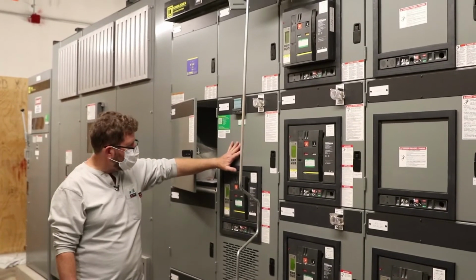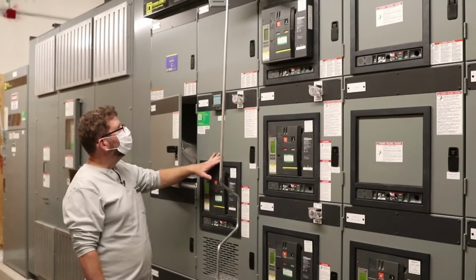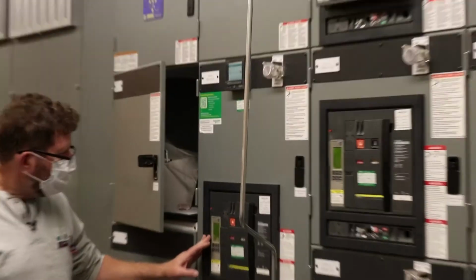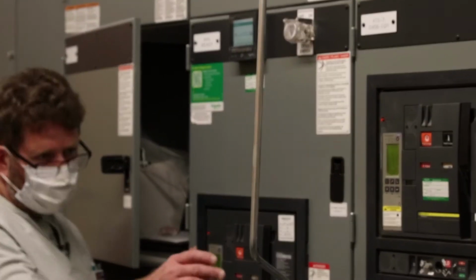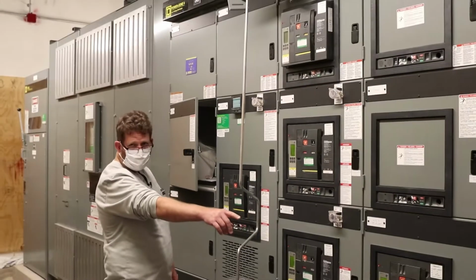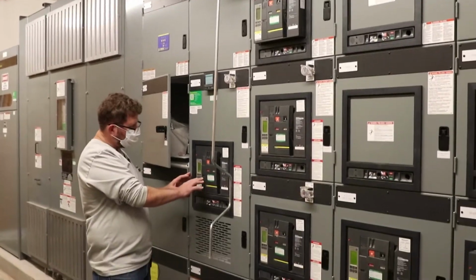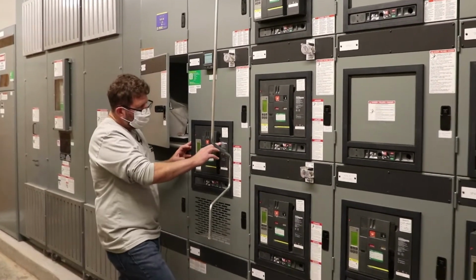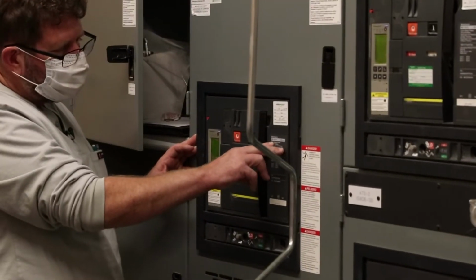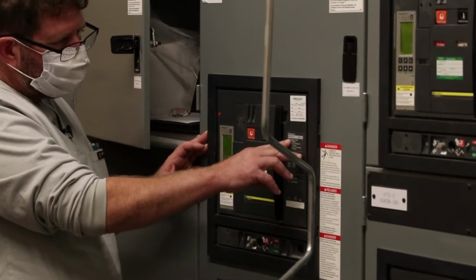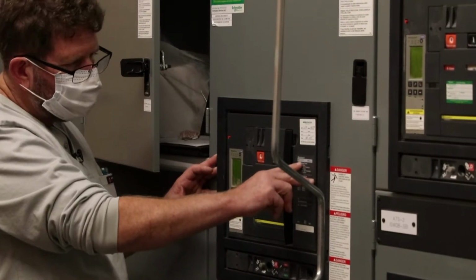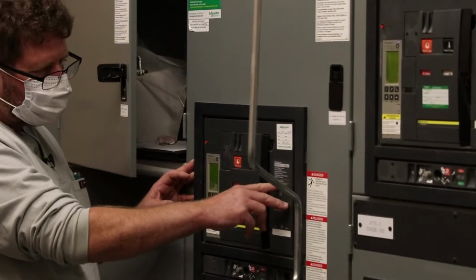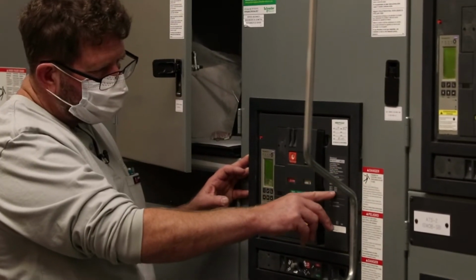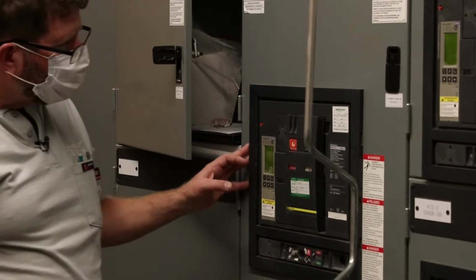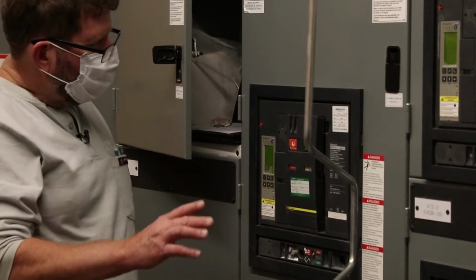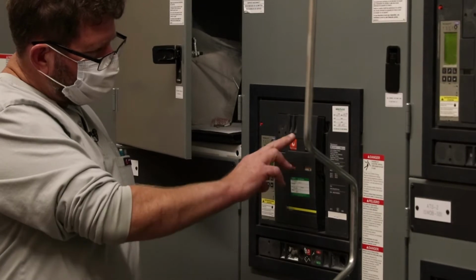So after section 1, you come to section 2. This is your main breaker. This is our Masterpact breaker. We'll go through it. We'll pull the spare breaker out and look at that a little more in depth. But just going through the front of the breaker, you have the nameplate, which tells you what frame it is and what rating it is. This is an NW style breaker. It's rated at 3200 amps, and the interrupting rating is H1, which happens to be 65 kA.